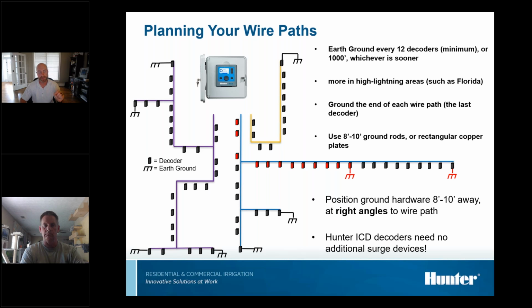Most newer jobs are going to be using what we call a ground plate, and I'll show that in a second. You still see a lot of people using ground rods, but here in Georgia, we've got red clay, and I used to think I was a strong guy and lifted weights, and I can count on one hand the times I was able to drive an entire 8-foot ground stake into the ground without it bending over sideways, just because the ground was so hard. So a lot of guys now have moved away from the ground rod and use a ground plate. I prefer the ground plate.